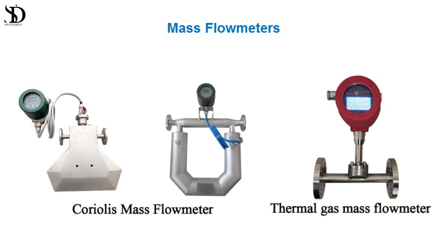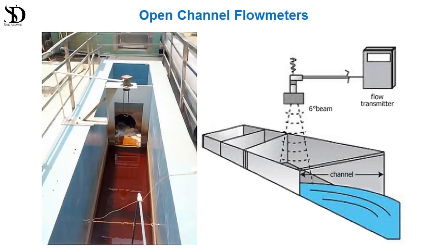4. Mass flow meters: measure the mass of the fluid passing through the meter. Coriolis and thermal flow meters belong to this category. 5. Open channel flow meters: primarily used for measuring flow rates in open channels such as rivers and streams. Weirs, flumes, and acoustic Doppler methods are employed.